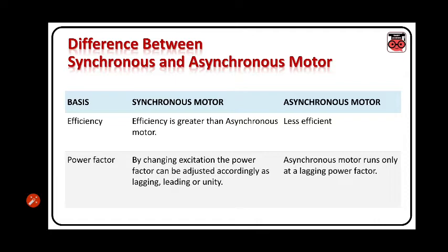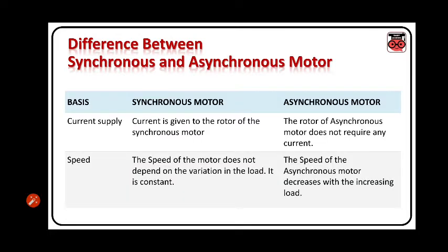Power factor: by changing excitation, the power factor can be adjusted accordingly as lagging, leading, or unity. In an asynchronous motor, it runs only at lagging power factor. Current supply: current is given to the rotor of the synchronous motor, whereas the rotor of the asynchronous motor does not require any current.